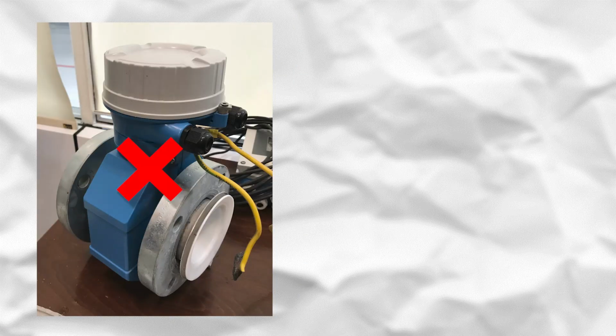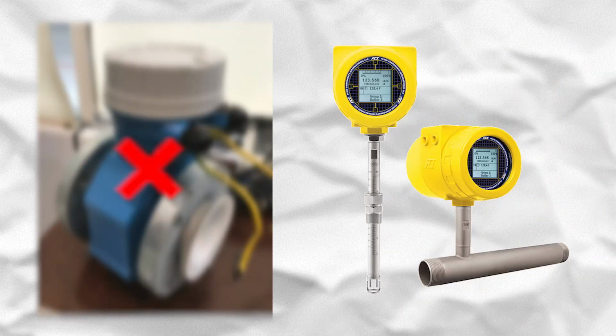Turn-down ratio, called rangeability, is the division of the maximum amount of a device measured by its minimum. Surprisingly, ignoring one of these factors would have an awful effect on the measuring. As an example, magnetic type flow meters cannot measure steam or gas, while thermal mass flow meters are the best choice to measure these services. Furthermore, magnetic type is applied for liquid whose conductivity is greater than 5 microsiemens per centimeter.